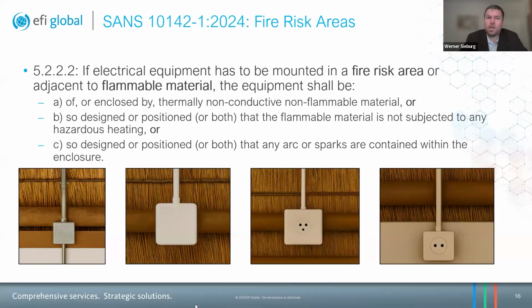So number B says it must be so designed or positioned or both that the flammable material is not subject to any hazardous heating. And here, I just want to draw the audience's attention to the fact that it's not that you have to do a certain thing, but you have to ensure a certain outcome. In other words, you have to ensure as designer of this electrical reticulation that the flammable material is not subject to any hazardous heating. The way in which you do that is entirely up to the designer. But adherence to this standard then requires that any location of the electrical installation that might fail must be as far as possible removed from this flammable material to prevent the hazardous heating.